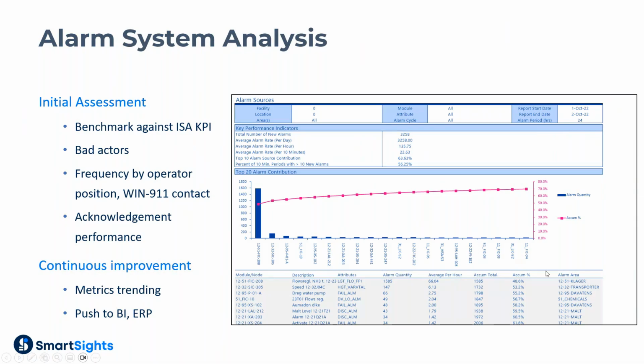Clearly this is something that's always up on the HMI. It's probably distracting, bothering, irritating operators, and can lead to fatigue or desensitization to alarms. So what we probably want to do here is re-examine what we're actually doing with this alarm. Do we even need this thing at all? Can we put an activation delay on it to help with the chattering, et cetera?